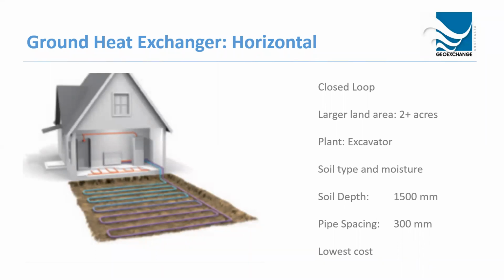Our problem here in Australia is that we're rejecting heat out in summer. And can you imagine rejecting heat out in the surface car park or something, where it is about 50 or 60 degrees? Then our heat can't escape from the ground loop. You've got this big thermal blanket over the top of it. It's just going to cook the ground. What happens first is you dry out the ground. The ground starts to crack, becomes more friable, and it's heat saturated anyway, so you won't be able to discharge heat into that area. So a horizontal loop could sneak under a driveway or go underneath something at some point which is sealed, but it should be a really small part of the overall length of the loop itself.